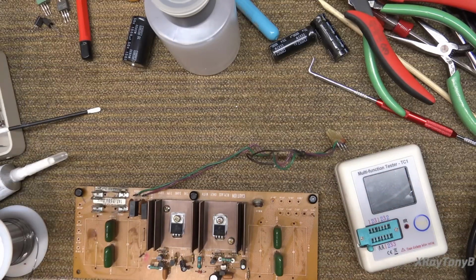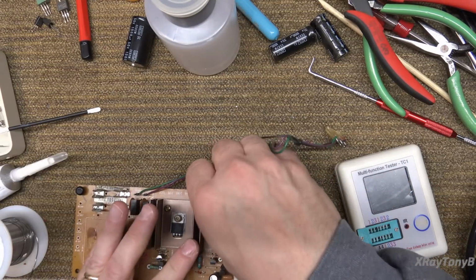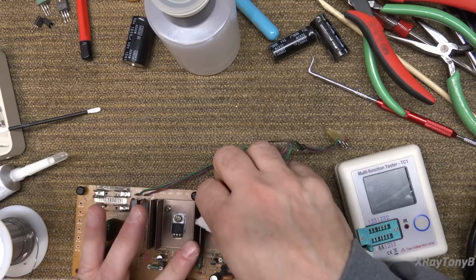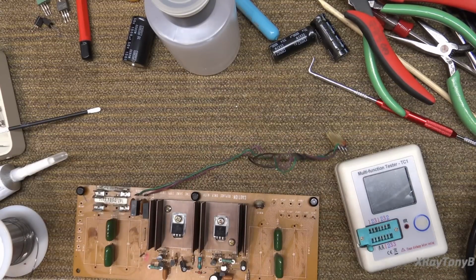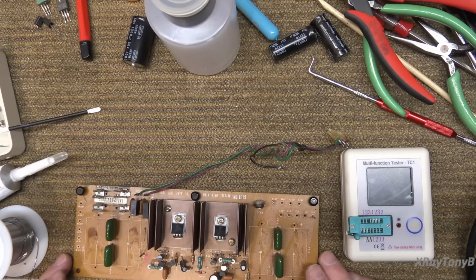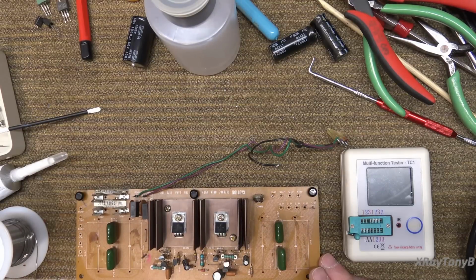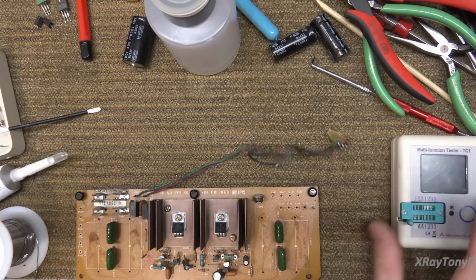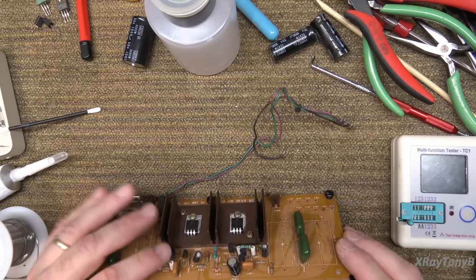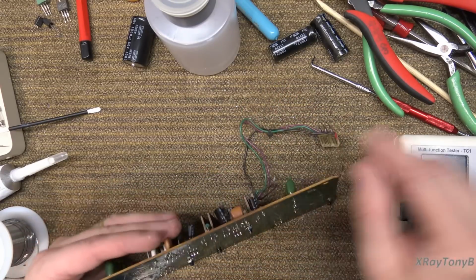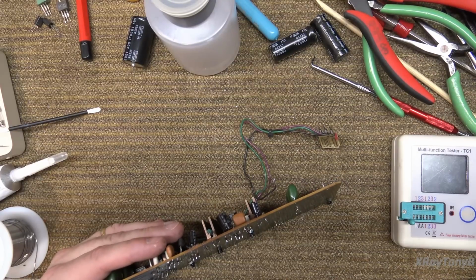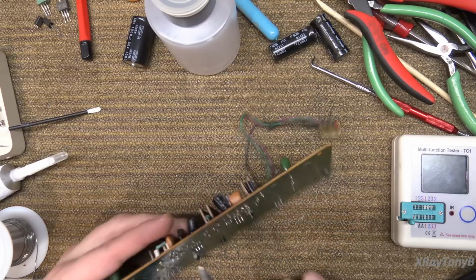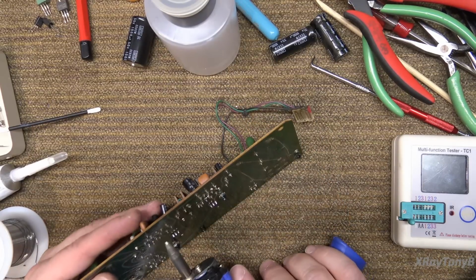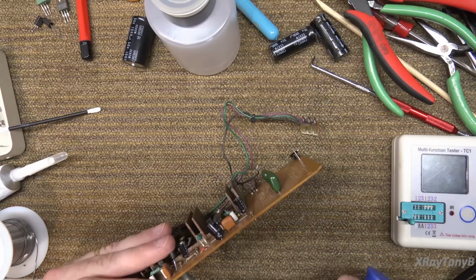So that's a story I share with the new guys sometimes when I go to work on this stuff, because it'll kill you. If you get across that, it'll kill you instantly. And then the primary voltage that drives all that is quite often 480 volt 3-phase power, and you can have a 100, and some of them even have up to a 200 amp circuit breaker, especially like some of the CAT scanners out there and so forth. They're no joke. And it's kind of what we work on every day. So you have to be careful.